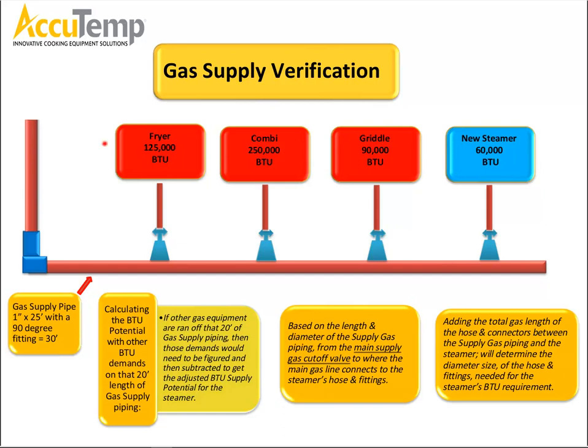Looking up here, let's say, for example, this is a brand new restaurant and they're trying to hook everything up. So, using the same supply, do you want a fryer at 125? Do you want a big combi, 250,000 BTUs, and then an AccuSteam Griddle, of course, at 90,000 BTUs, but you also want to stick a steamer in there at 60,000 BTUs.